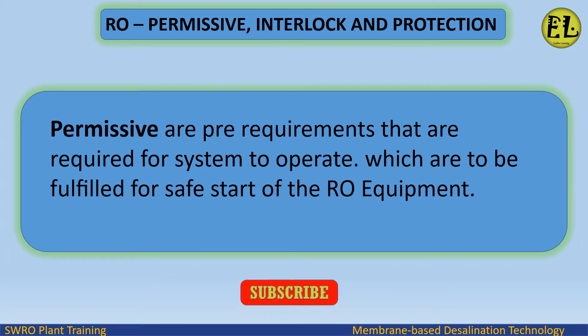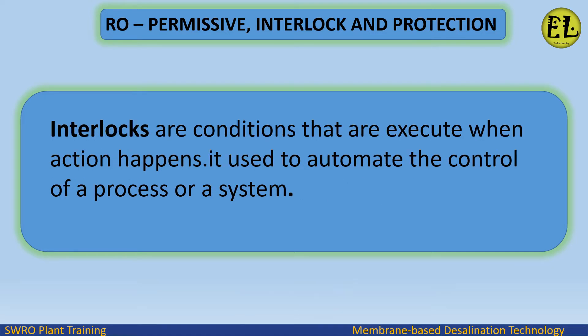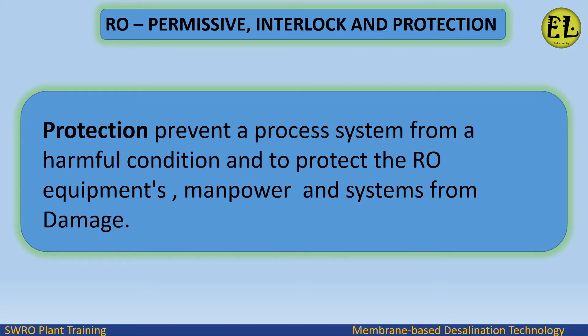Permissives are pre-requirements that are required for the system to operate, which must be fulfilled for a safe start of the RO equipment. Interlocks are conditions that are executed when an action happens, and are used to automate the control of a process or system. Protection prevents a process system from a harmful condition and protects the RO equipment, manpower, and systems from damage.